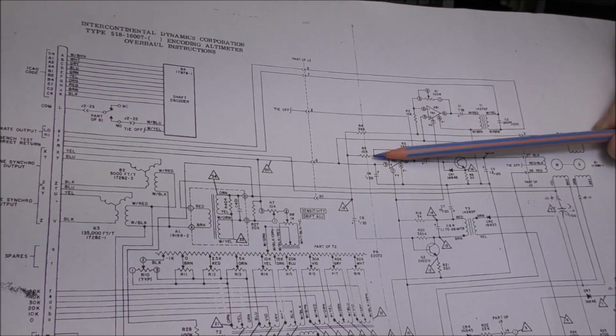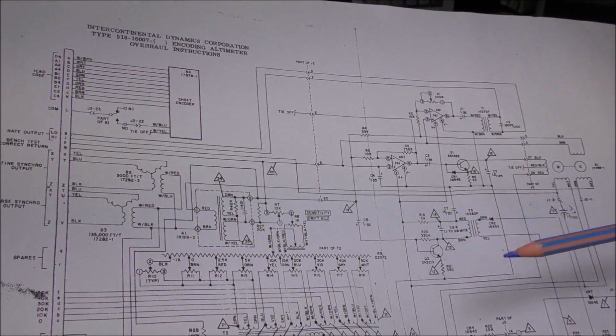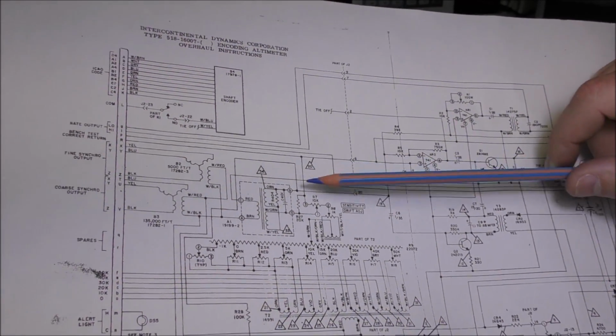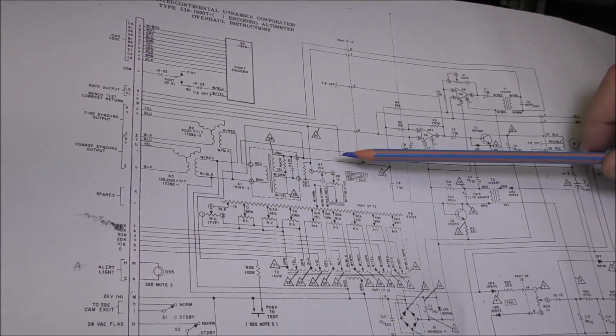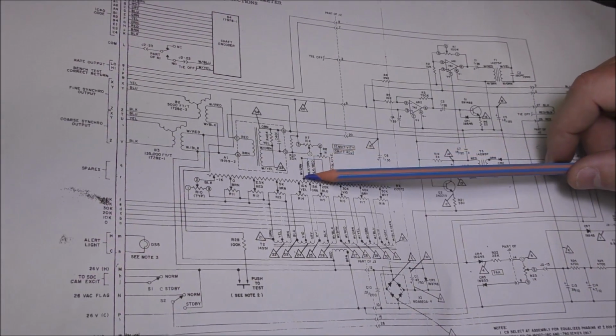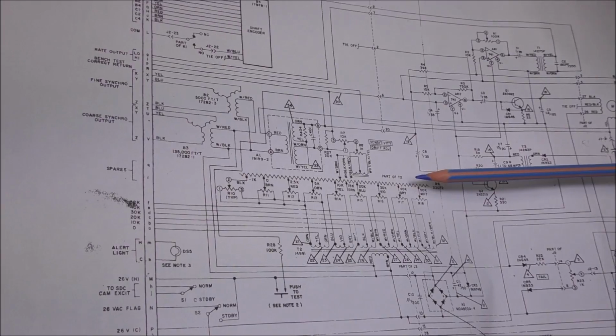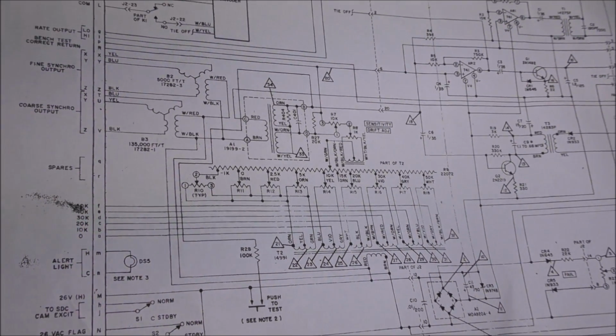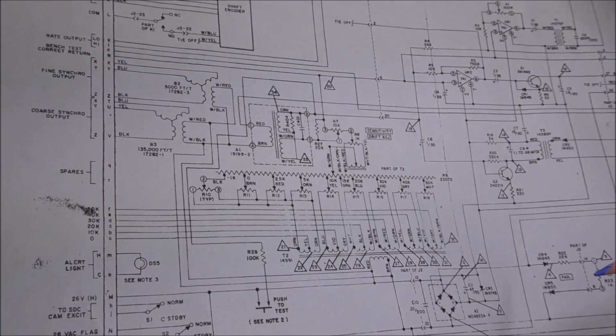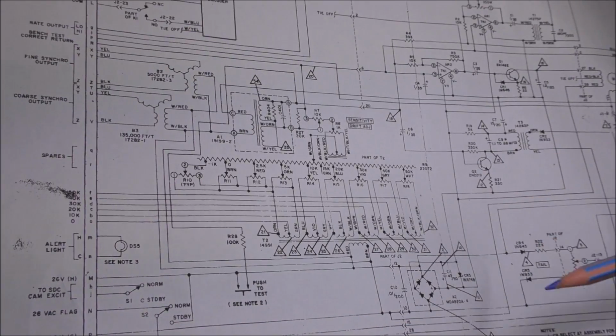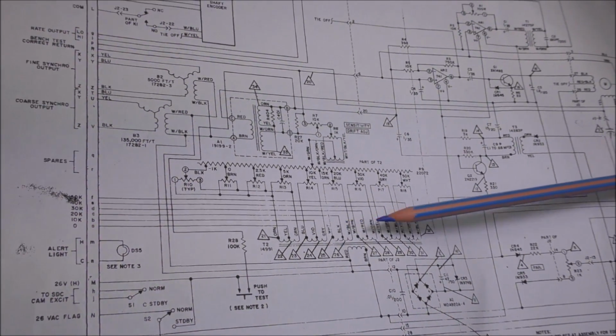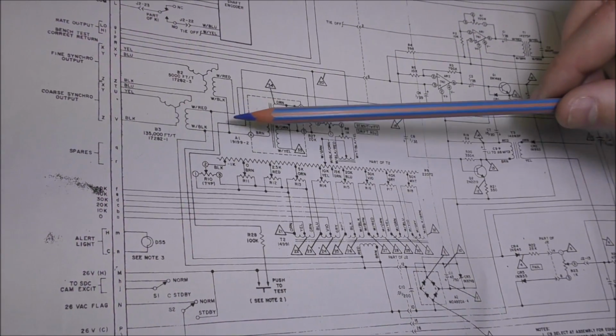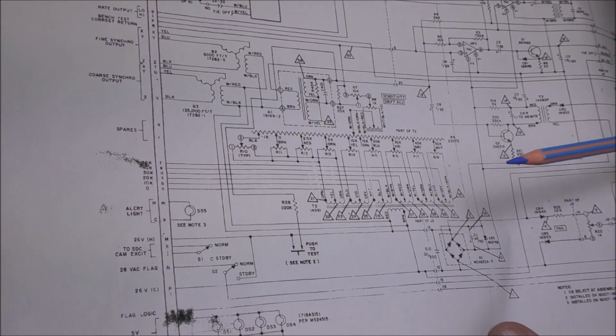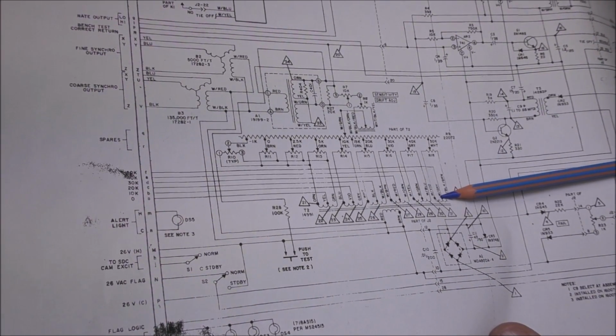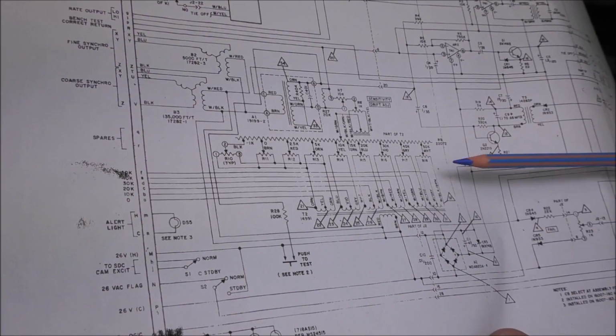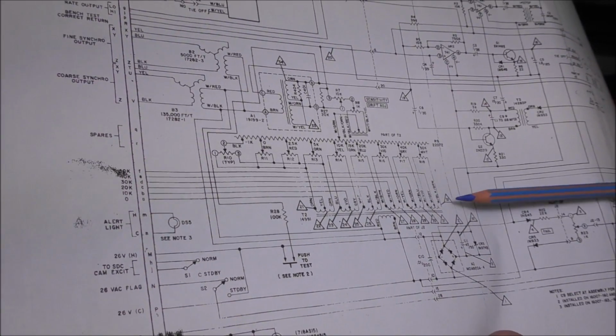The input of the amplifier is connected to the tachometer, we just seen. It is also connected to the pick-off sensor, of course, which is here. And you can see that the second input of the pick-off sensor is connected to this potentiometer. This potentiometer is the adjustment of the linearity. It is possible to adjust the voltage at each particular tap of this potentiometer using these trimmers here. These trimmers are supplied with this transformer, and the primary of the transformer is connected to the 26 volt AC, and it is also possible to activate or not the correction, because the middle point of the secondary is available on the rear connector. If you don't connect this line to the ground, this will not have any effect, because this secondary will be left open.